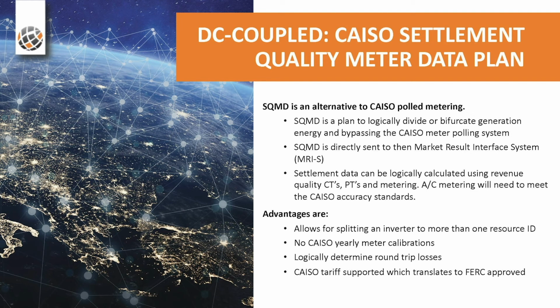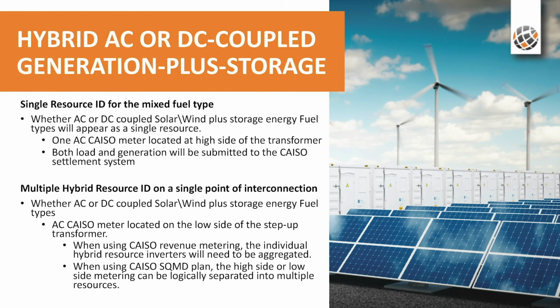Just to wrap up, the single resource ID for a mixed fuel type, whether AC or DC, you have one resource ID, which means only metering on the high side of the transformer. However, if you wanted to take that hybrid resource, either AC or DC coupled, and you wanted to serve multiple PPAs, then all of the metering needs to move to the low side. And then again, if it's AC coupled or AC hybrid, the PPAs and the metering need to be on the inverter boundaries, where you cannot share inverters between PPAs. And again, the hybrids will also be polled by the ISO if you wanted to, or we can do an SQMD plan by slicing up inverters.